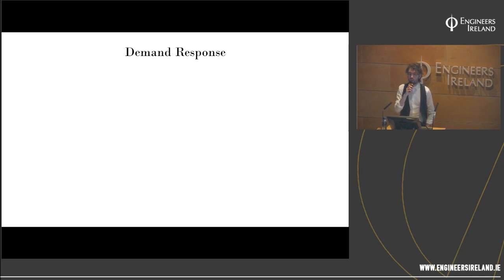That's because when you extract power from the wind turbine to provide the inertial response, they're taking it off optimum in terms of its energy capture capability, and so it has to go back to that. Yeah. But also, like with a synchronous machine, that will have an energy recovery period per se, because when it gives a synchronous inertial response, it slows down to inject that energy, and then when the system gets back to 50 hertz, that speeds back up. So there's give and take with every machine. But the thing with the wind is that it's decoupled from the frequency to an extent, and also there's other stuff at play, like you say, because it's hopping back to that maximum power point tracking.